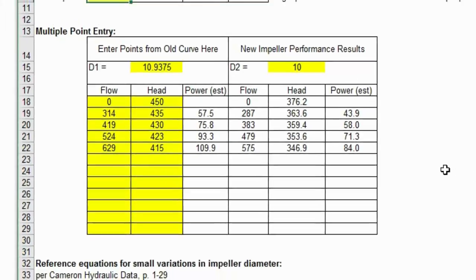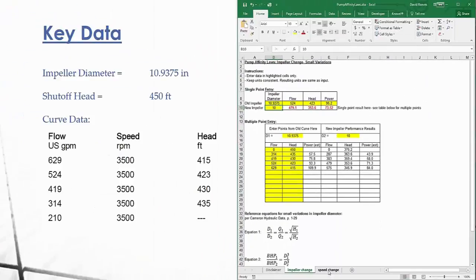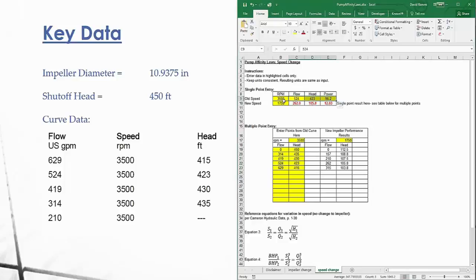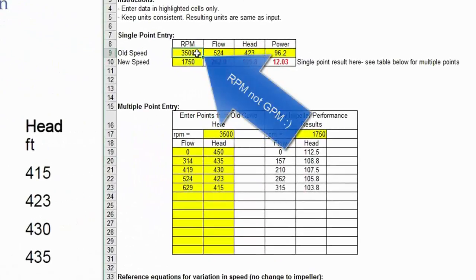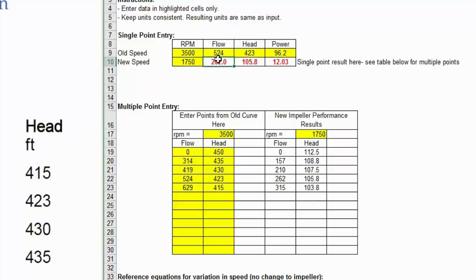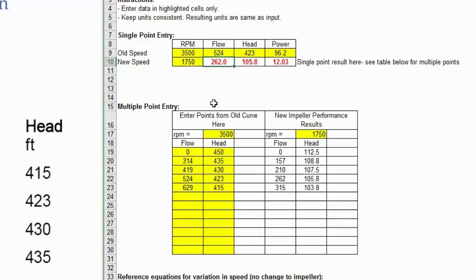Same thing goes for the speed tab. We've got all the same data points in here. If you started out at 3500 RPM, and say we wanted a two-speed pump, what's that kind of pump going to do at 1750 RPM? Well, the flow is going to split in two. Remember, flow was proportional to speed. Speed is proportional to RPM. And power is proportional to the cube of flow and to the cube of speed.